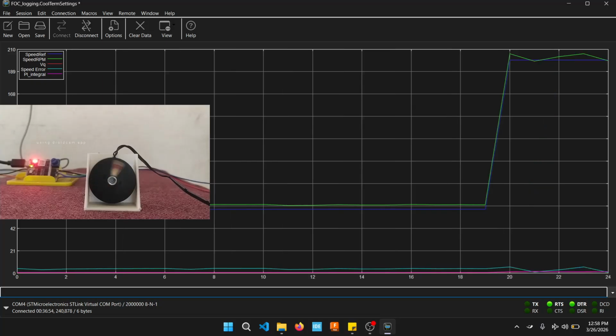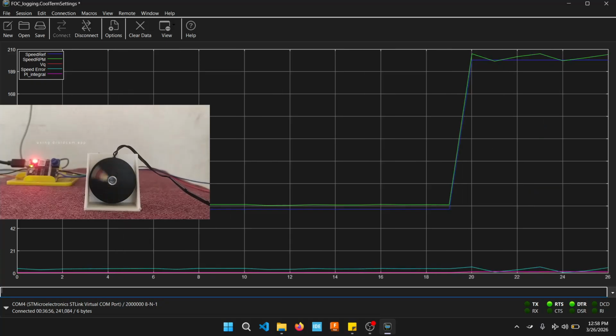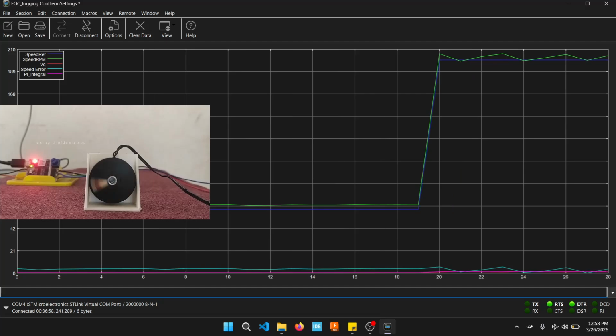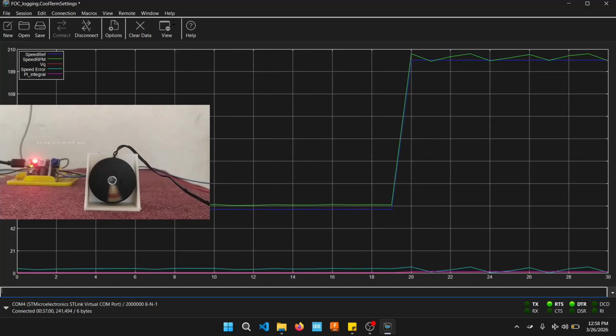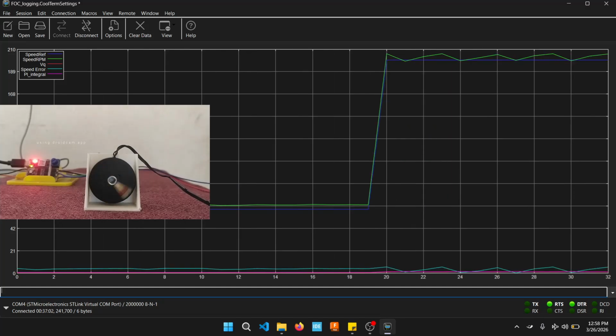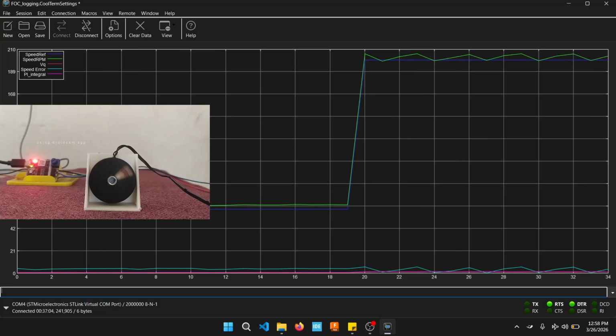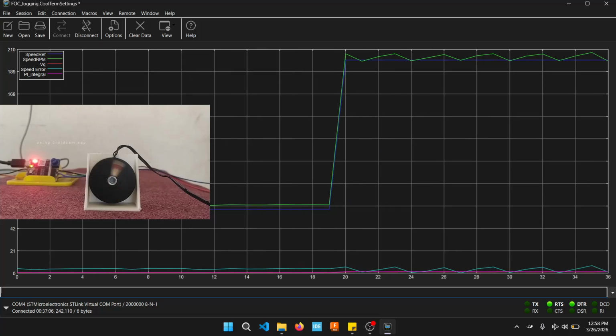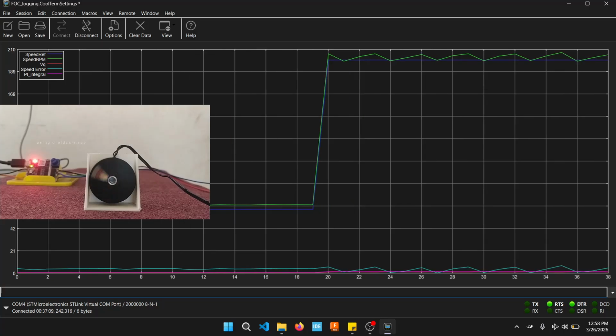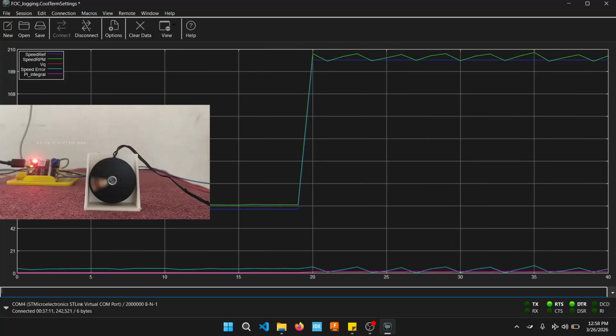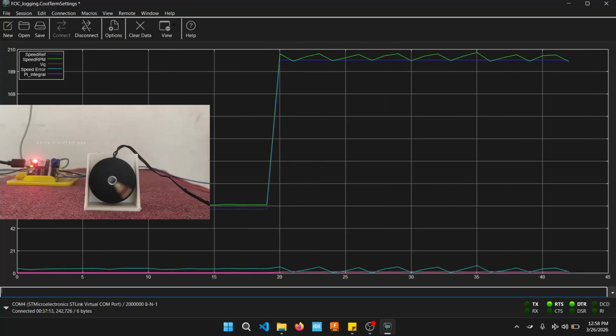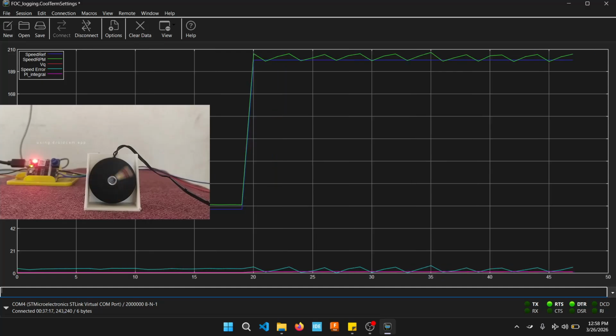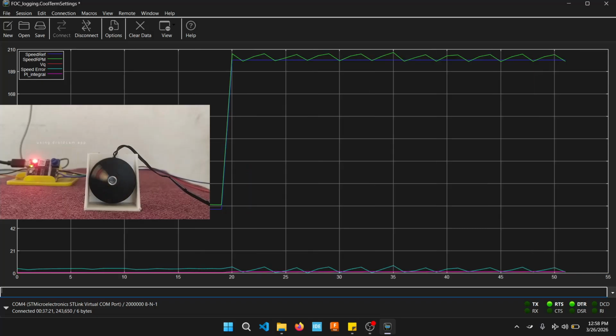You can see there's a little bit of oscillation, but the controller is trying its best to keep up with 200. Since this is a low RPM motor with 7 pole pairs, these values will be in different regions, so we should possibly think of gain scheduling.